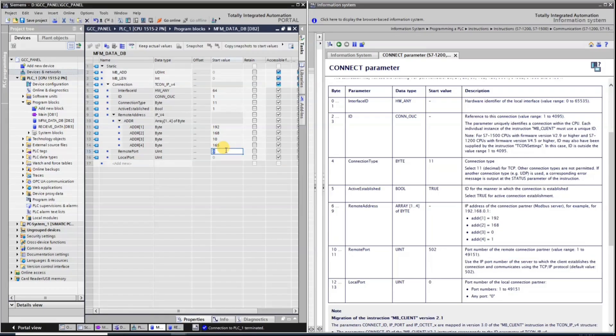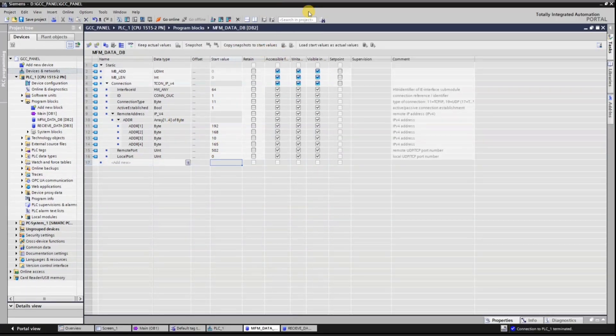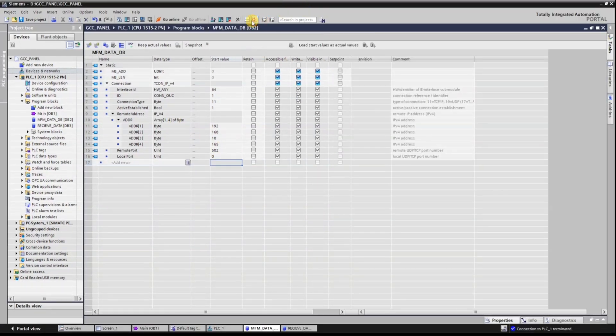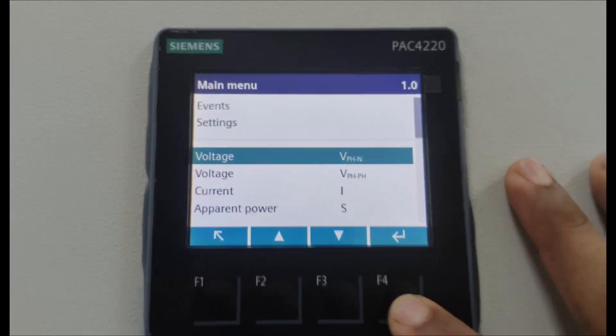In remote address you write the IP of the server where you want to receive data. Remote port is normally the default port 502 and local port is 0. Now we set the IP in our multifunction meter.